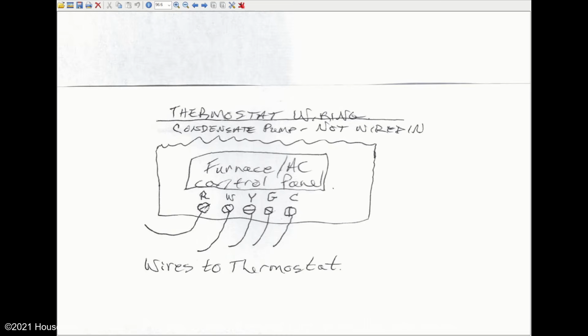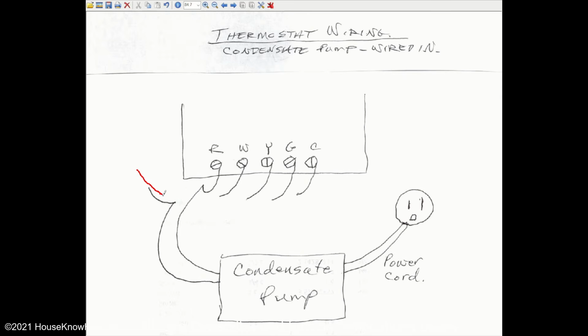Okay. So these control panel boards are going to have several connections on them that go to the thermostat. All you have to do to get a condensate pump wired in is to disconnect this wire that typically goes to R, hook it up to one of the wires that goes to the condensate pump, and then the other wire to the condensate pump goes to that R terminal. Simple, yet it's not done in many, many cases.